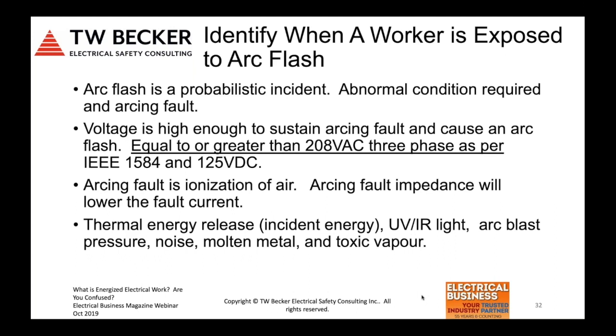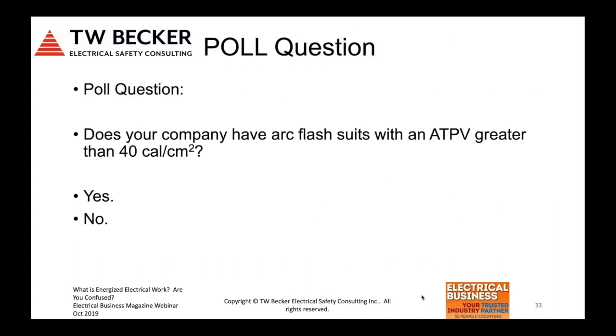We get an arcing fault, there's impedance, and we'll have a lower fault current because of that. This is some important information with respect to when we're determining the PPE that we need. And again, the effects are a thermal energy release called incident energy, UV light, arc blast pressure, noise, molten metal, toxic vapor. So the first poll question.